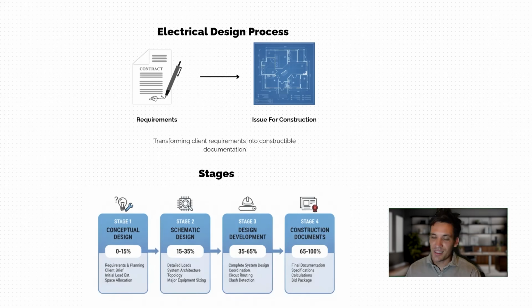The electrical design process occurs in a couple of specific stages. We start off with the conceptual design stage, which is we look at the initial client brief and client requirements and turn these into an initial system design, looking at what the loads are going to be, where the equipment's going to fit, what sort of equipment we're going to need, and draft more or less a simple single line diagram. We then progress.